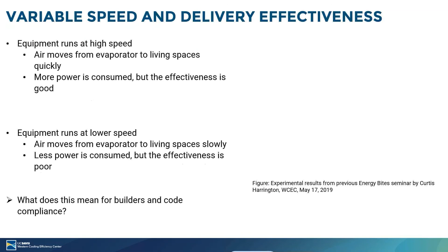And so say you're running your equipment at a high speed. What's going to happen is air moves from the evaporator to the living spaces quickly. And this uses more power, but the effectiveness is good, the delivery effectiveness. Say you run your equipment at a lower speed.